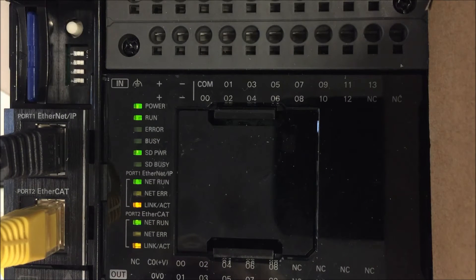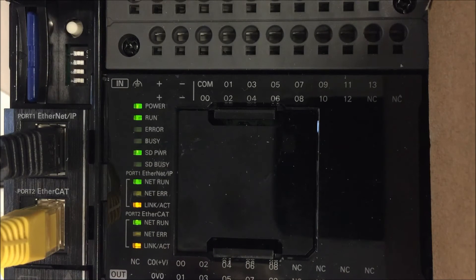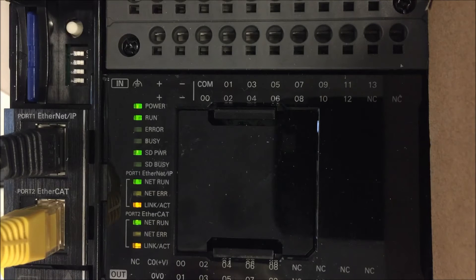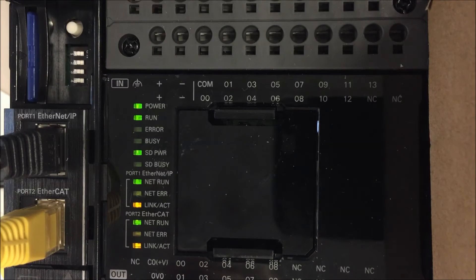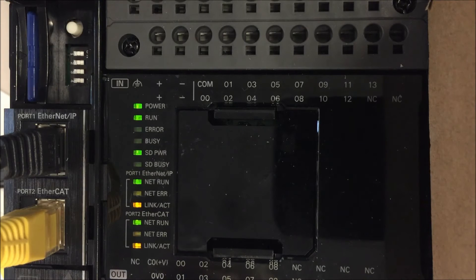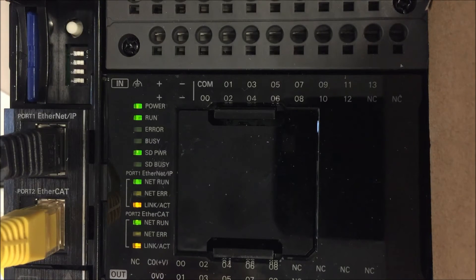To verify the data for my backup procedure, I've set dip switches 1, 2, 3, and 4 all off and I'm going to press the SD memory card power supply button for 3 seconds and it will do the verification process.